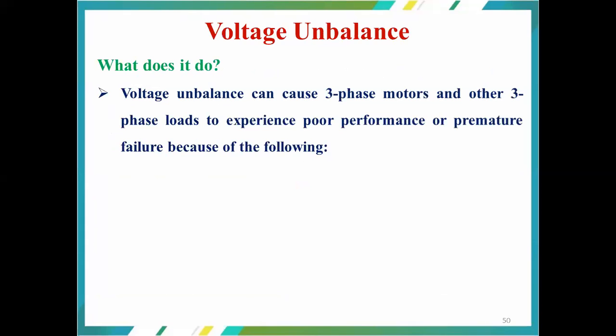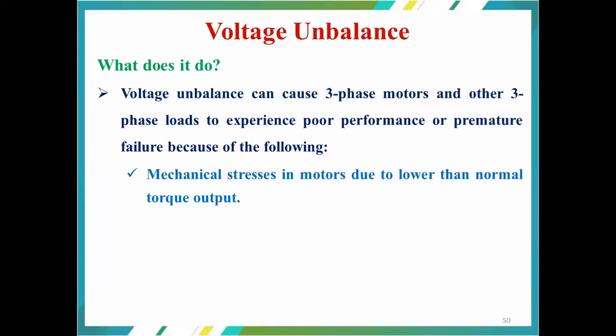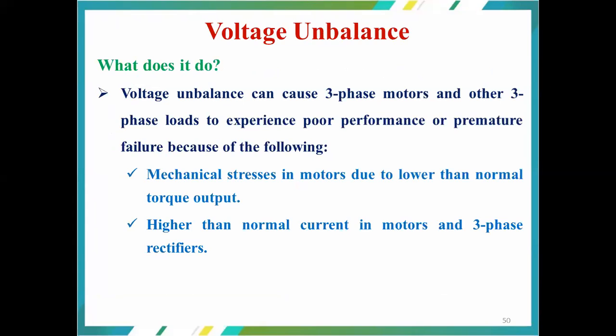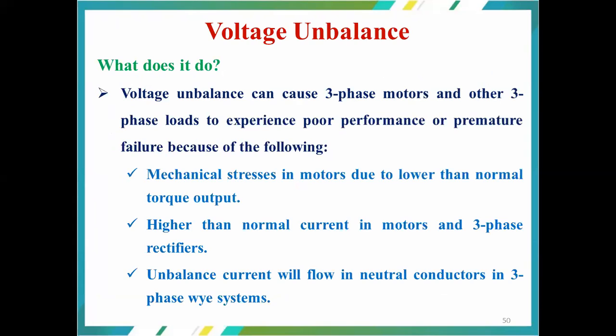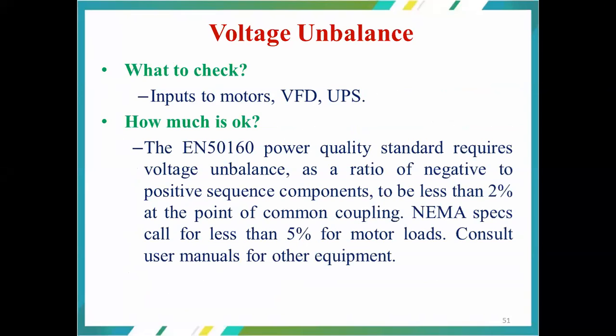The ill effect of this unbalance is that it can cause 3-phase induction motors and other 3-phase loads to experience poor performance or premature failure, because of mechanical stresses in motors due to lower than normal torque, and higher than normal current in 3-phase motors and 3-phase rectifiers, which may result in overheating of the terminal points, cables or power devices. Unbalanced currents will flow in the neutral conductors in a 3-phase Y system, which is going to increase the neutral to earth potential. So we check the voltage unbalance at the inputs to the motors, VFDs and the UPS.